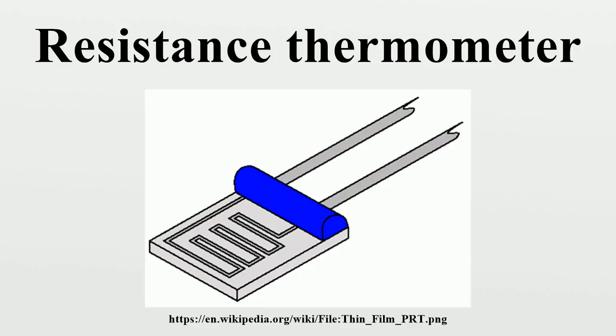Lead wire resistance can also be a factor. Adopting 3 and 4 wire instead of 2 wire connections can eliminate connection lead resistance effects from measurements. 3-wire connection is sufficient for most purposes and almost universal industrial practice. 4-wire connections are used for the most precise applications. Advantages and limitations.